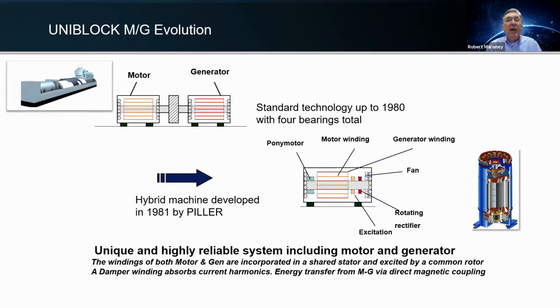In 1981, Piller came up with a hybrid machine and actually unified it into a single system. You'll see it here in a minute. There's a picture there on the right. But it allows for a more compact, reliable, cost-effective system that allows for that power factor, voltage regulation, and harmonic mitigation and correction as we go through the system.